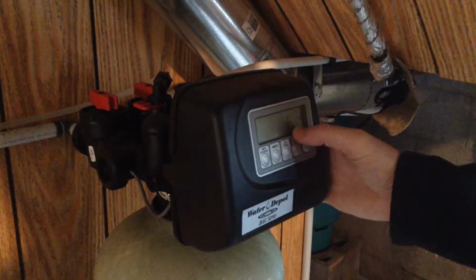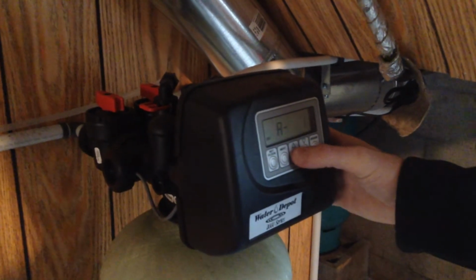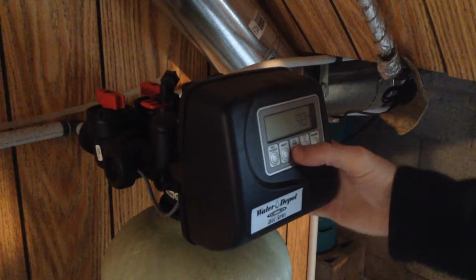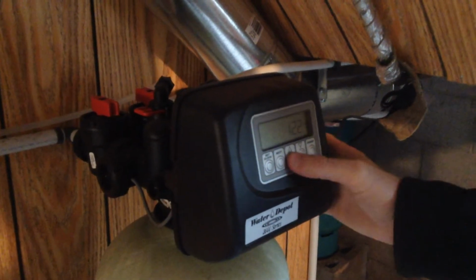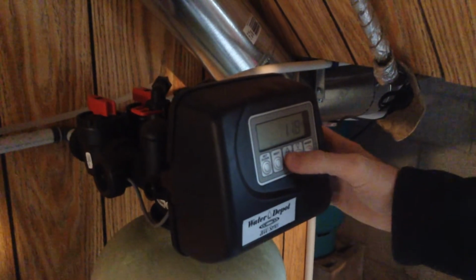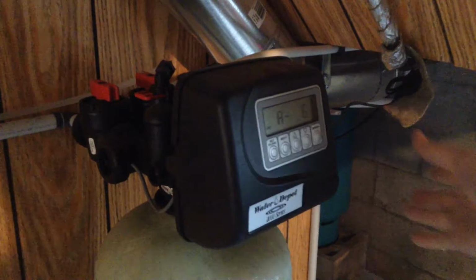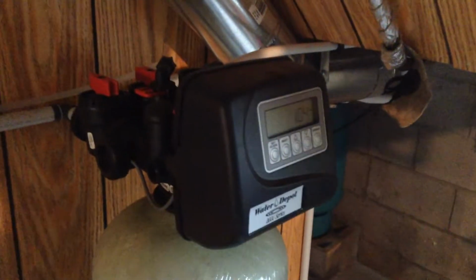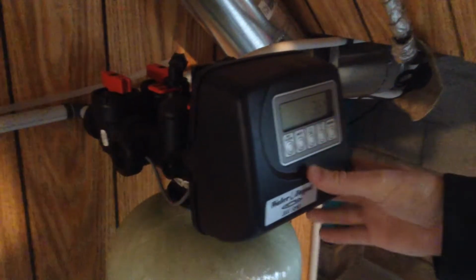Those numbers are right. There's a low day and a high day, and it's just taking averages. Your low day is 61, and your high day is 122, which is pretty good for averages. There's nothing irregular about those numbers. If we saw a number like 350 or 500, we would know that something was going on, like a leak.